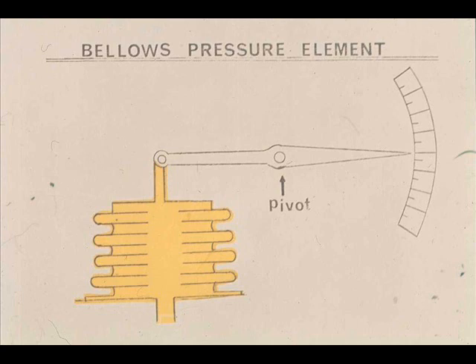And the bellows, which is also a pressure sensing device, operates on the principle that any difference in pressure between the inside and outside of the bellows will result in compression or expansion of the bellows. This movement is translated by linkage to a pointer, which moves up or down a scale to indicate a change in pressure.